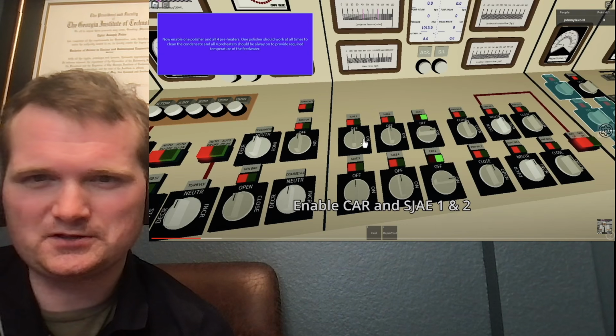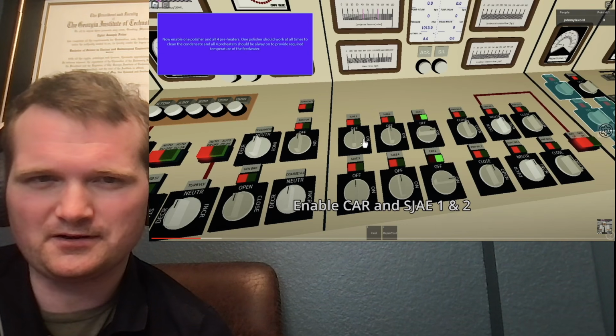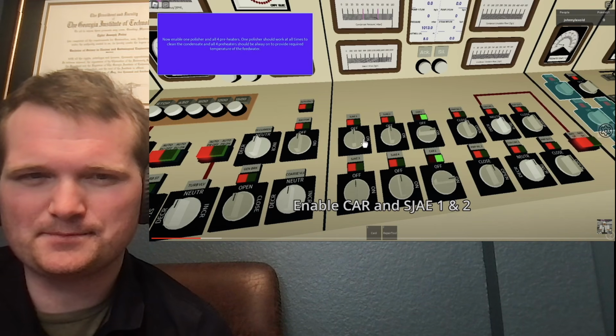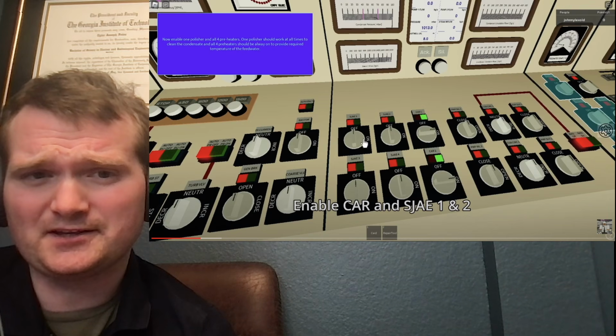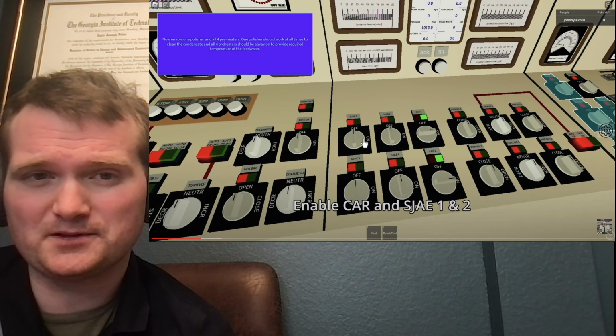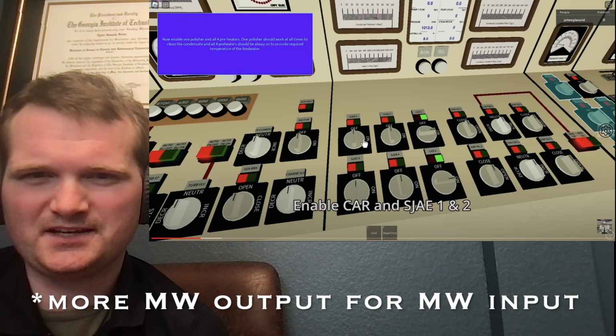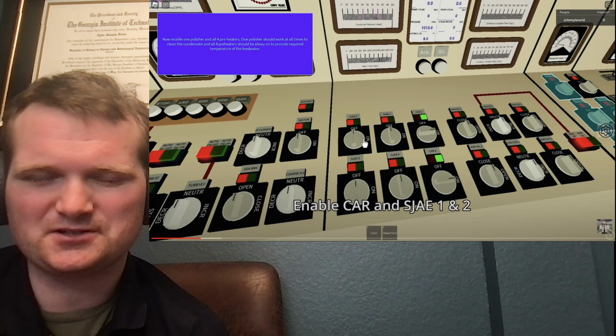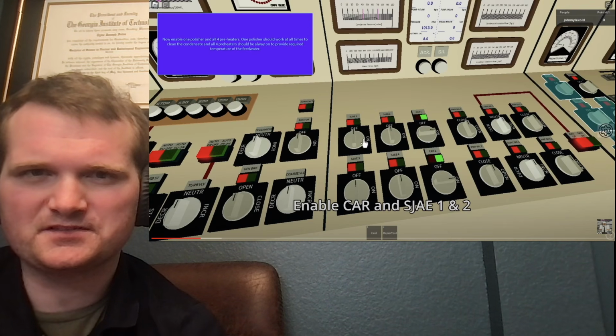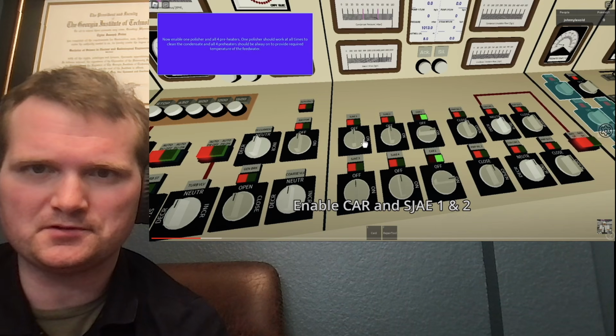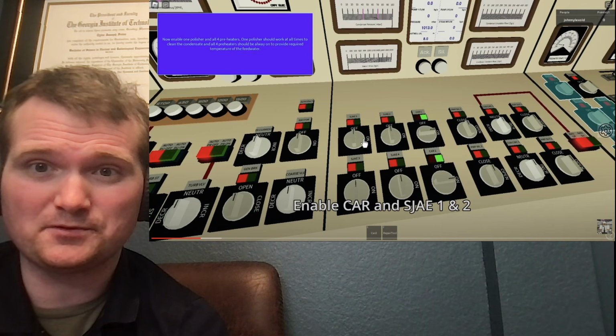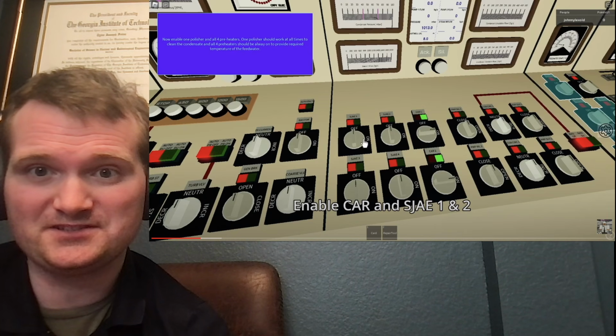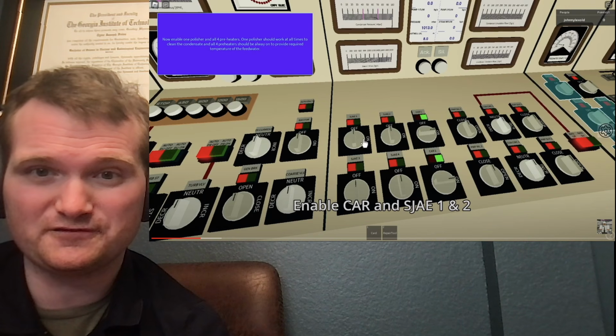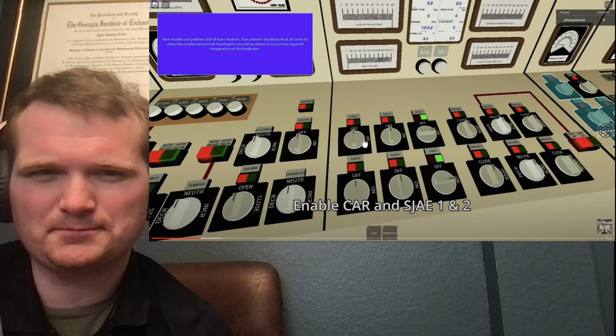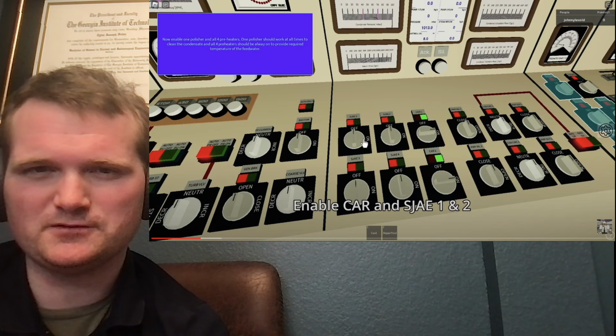So right here, enable CAR and SJAE. So CAR is a condenser air removal, just a vacuum pump to keep the condenser at a vacuum. Keeping your condenser at a vacuum is crucial to optimizing thermal efficiency, basically producing more megawatts. Now SJAE, same idea, steam jet air ejector, is to maintain vacuum in the condenser. Now, as far as difference, steam jet air ejectors use steam to entrain and remove non-condensable gases by creating a vacuum through high velocity steam, whereas vacuum pumps use mechanical means such as vanes or diaphragms to physically pump the air and gases out. The air ejectors are cheaper, less likely to break down because there's less moving parts involved, but the CAR's vacuum pumps are more precise.